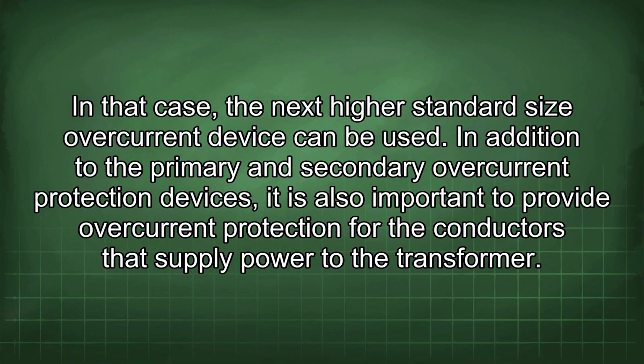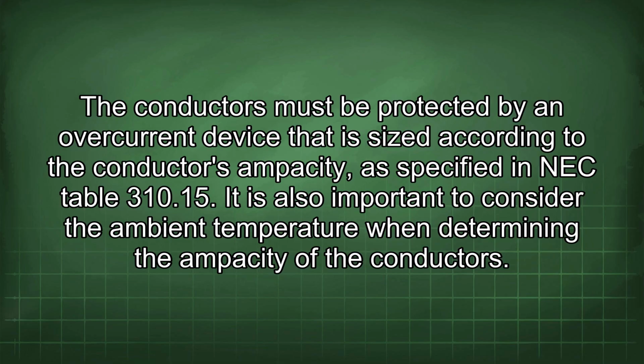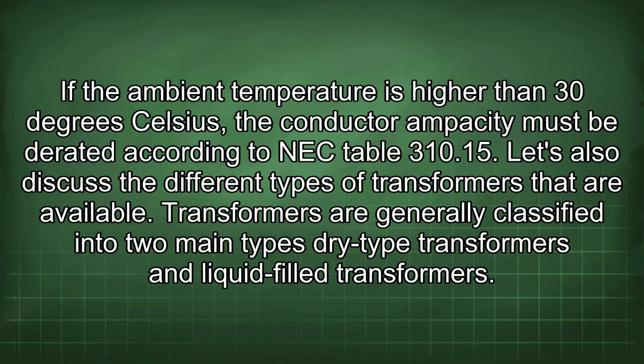In addition to the primary and secondary overcurrent protection devices, it is also important to provide overcurrent protection for the conductors that supply power to the transformer. The conductors must be protected by an overcurrent device that is sized according to the conductor's ampacity, as specified in NEC Table 310.15. It is also important to consider the ambient temperature when determining the ampacity of the conductors. If the ambient temperature is higher than 30 degrees Celsius, the conductor ampacity must be derated according to NEC Table 310.15. Let's also discuss the different types of transformers that are available.